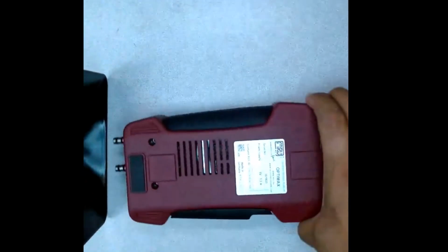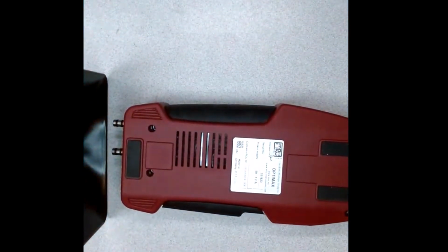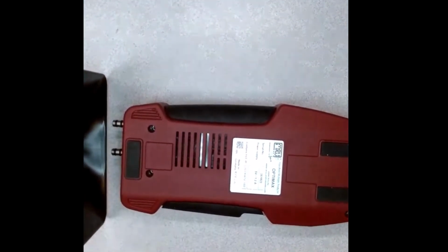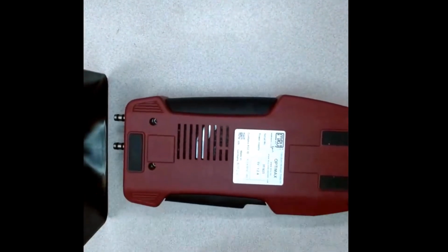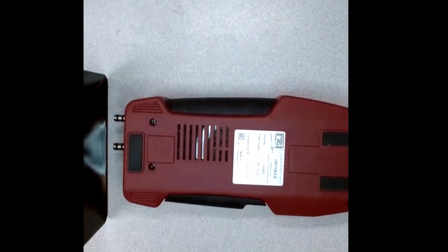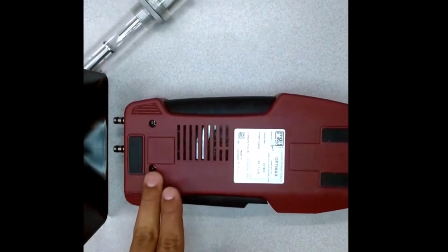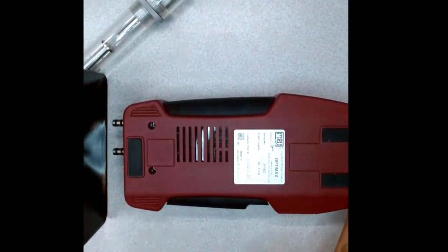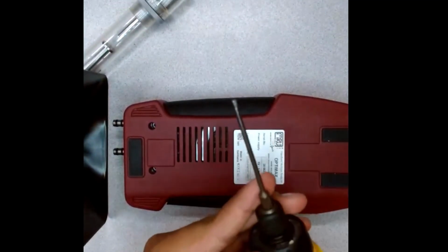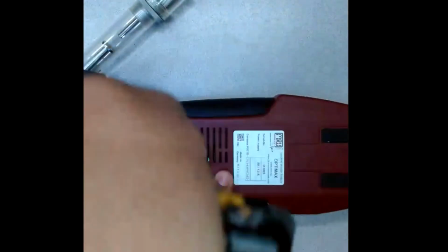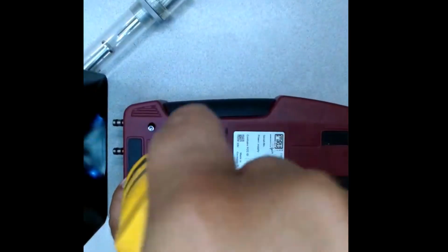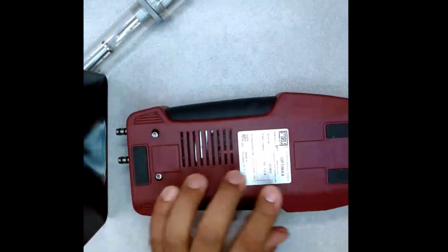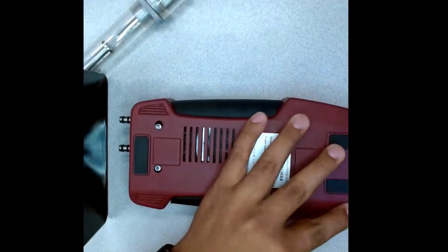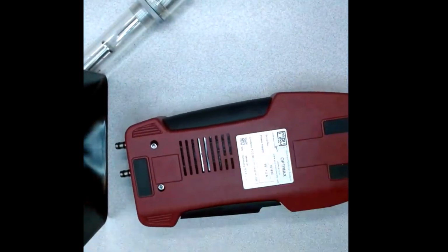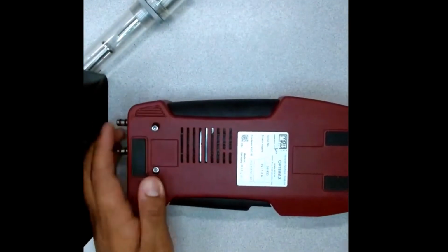And then when we open it, we turn it over and then turn it on its side here. So the condensate trap comes out towards us. It comes out of that side. And then these right here are the bolts holding it together. These are Allen keys. So just hex nuts like that, really small. So 4 of them at the 4 corners.